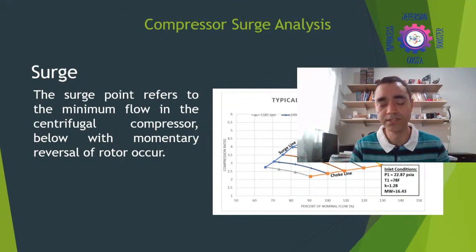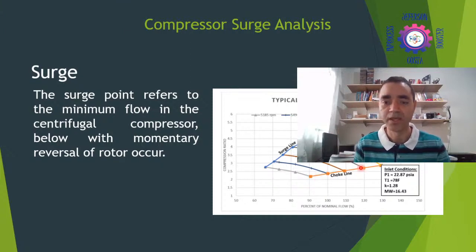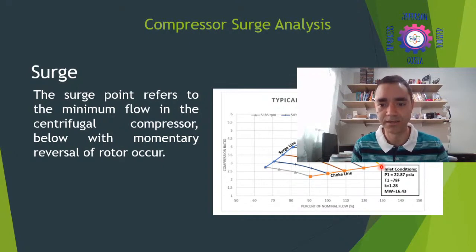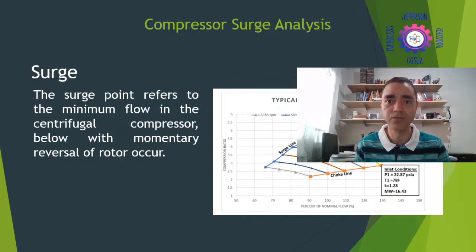On the other hand, when talking about compressors, you must have the system resistance matching what is expected for the compressor operation. If you don't have enough restriction, the compressor can go to the other side of the chart — the choke line or stonewall conditions — meaning the compressor is delivering far more flow than it was designed for, which also causes vibration and can lead to equipment failure. We want to avoid at any cost reaching both the stonewall line and the surge line, and to do that we have some kinds of control.